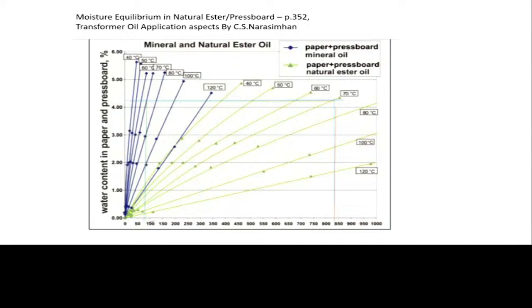You can see very clearly the ester oil figures are shown colored green. And you can see if you take 4% moisture on paper, for instance, I have drawn a line there parallel to 4%, around 4.2% or so. You can see at 4.2% and 70 degrees, if you see the blue line, that is the mineral oil, you hardly have about 100 ppm, less than 100 ppm. That is the moisture in oil.